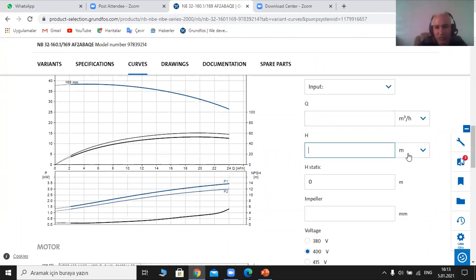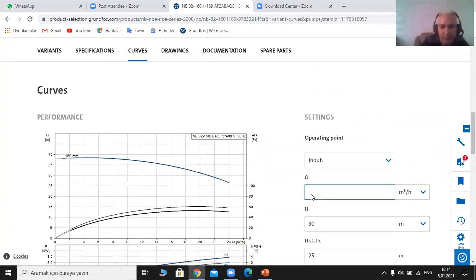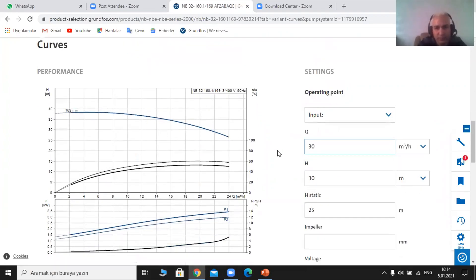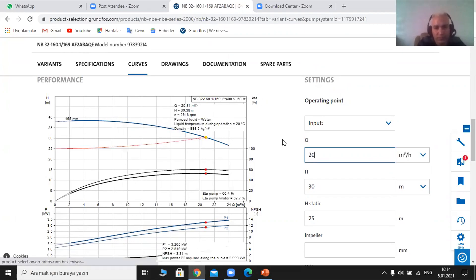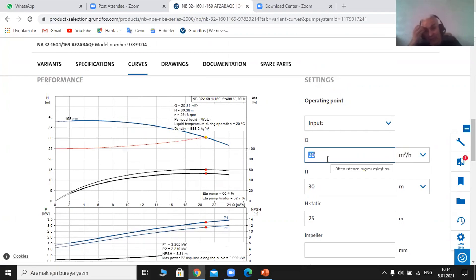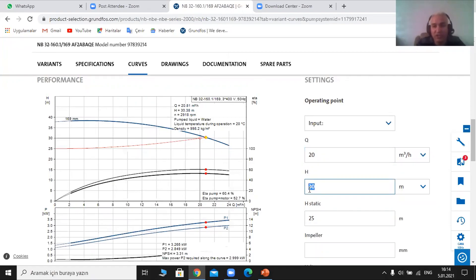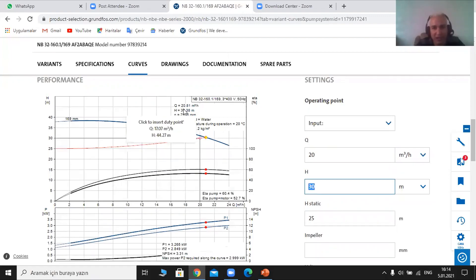We can change our input to have different outputs. The Q is 20, the total head is 30, the static is 25. When we put 30 for the flow rate it is not applicable because this pump curve is not applicable for 30. This is what we are talking about all the time — we need to choose accurately based on the flow rate. If we put a value for the head that is not accurate, within implementation it doesn't work properly, so performance is really bad and losses are high. For the variant: 20.81 flow rate, head 30.38, RPM 2,918.